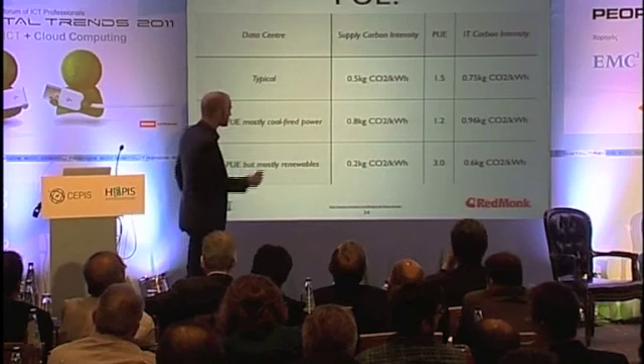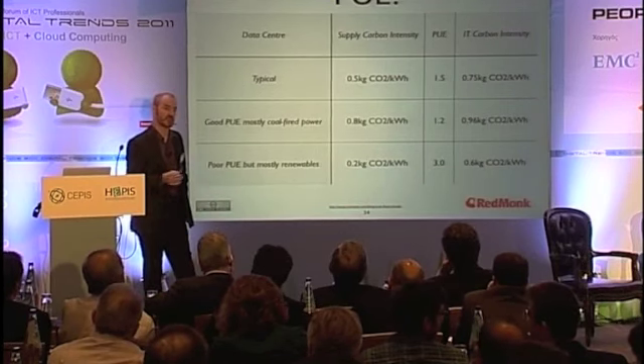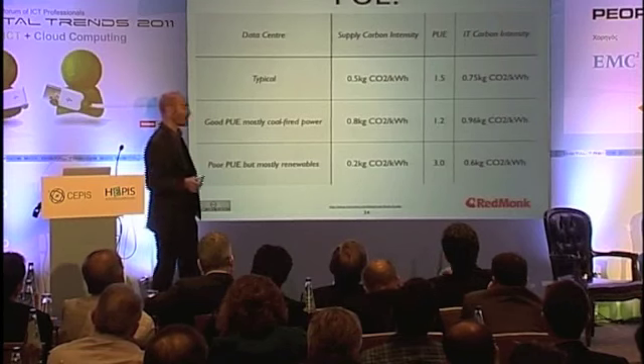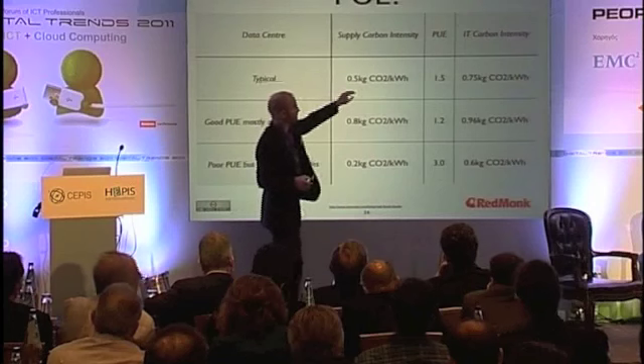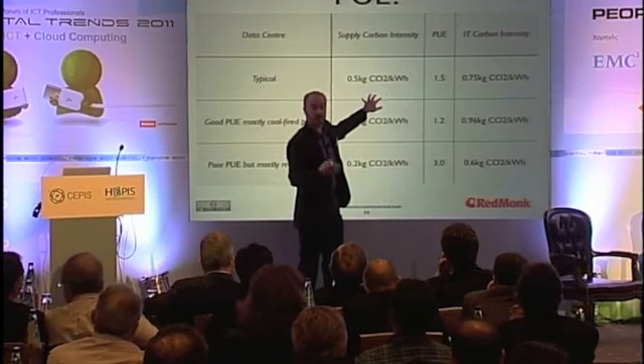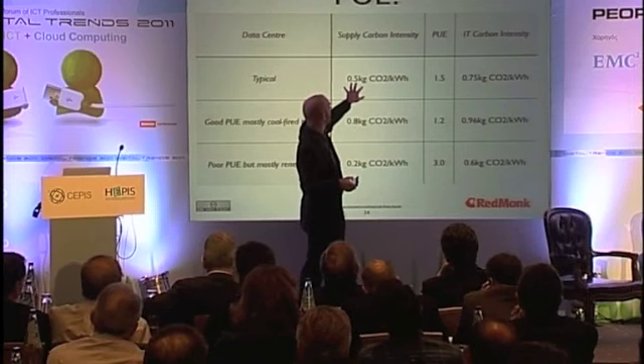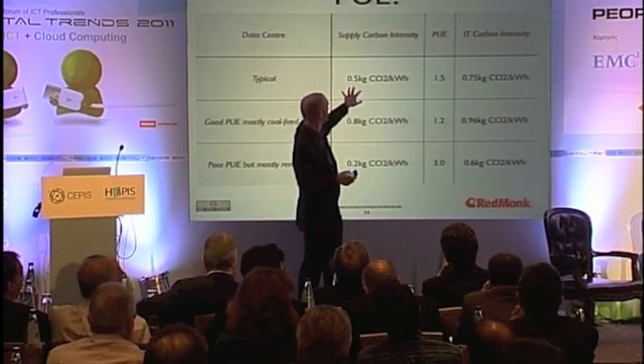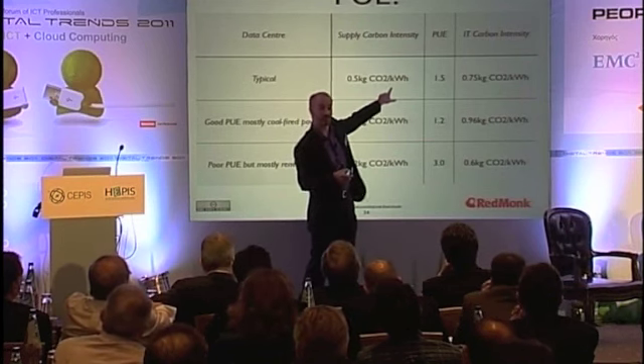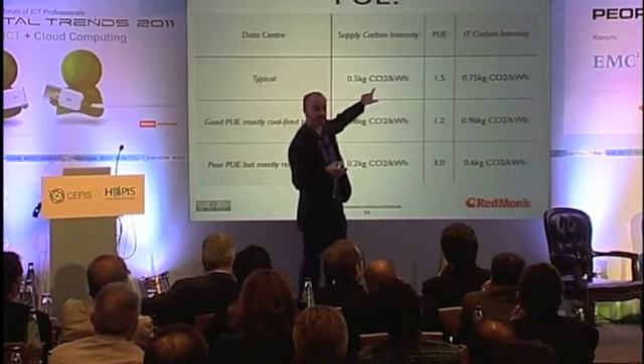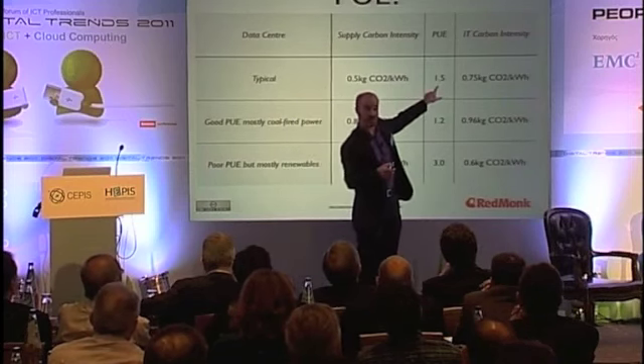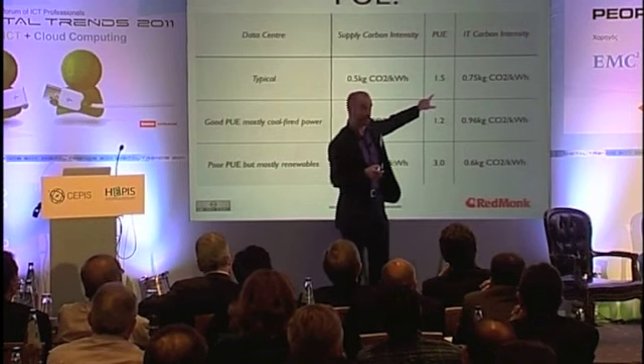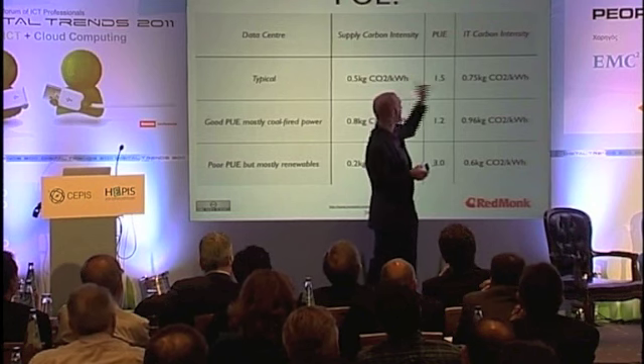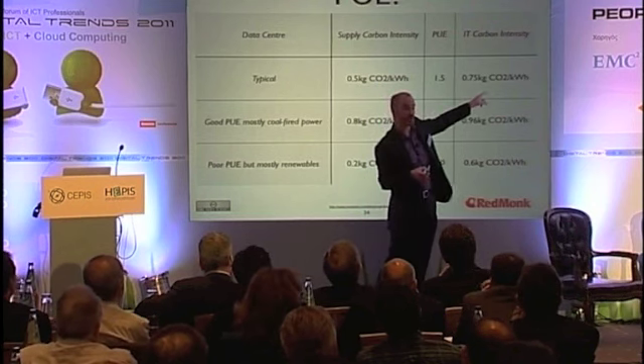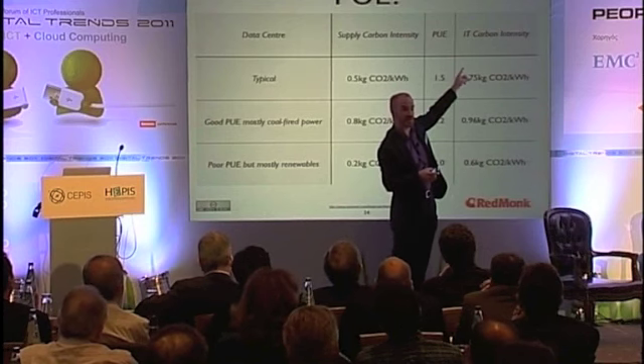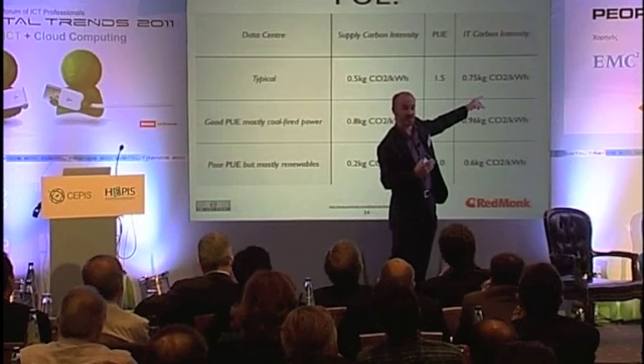Another issue, and I'm sorry this is a little bit complex, but I'll walk you through it. Another issue with PUE is it takes no account of carbon. So, top line is a typical data center in a European country where the supply of power causes a certain amount of CO2 per kilowatt hour. That's not unusual. That's a pretty average figure. So if the typical data center has a PUE of 1.5, which is quite good, then we get 1.5 by 0.5, we get 0.75 kilograms CO2 per kilowatt hour as the IT carbon intensity. It's how much the IT equipment is producing in terms of CO2.